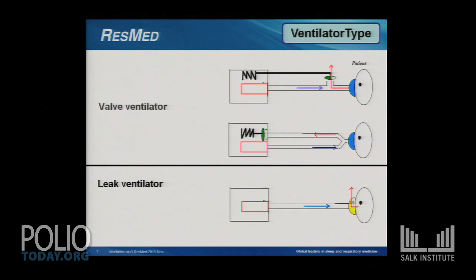Now, if you notice here on the valve ventilator, there are no holes in the mask. And you'll notice those masks are generally colored by the manufacturer. They usually make them blue. As a heads up, this mask does not have any holes in it for exhaled air. On the other hand, if you're using what we call a leak ventilator, there will be ports in the mask, so the exhaled air can escape out of those ports. But that's why we need that minimum PEEP or EPAP of at least 3 centimeters to flush that exhaled air out of those ports.